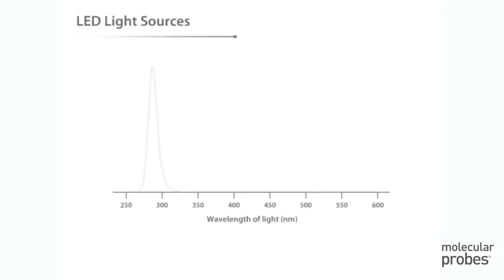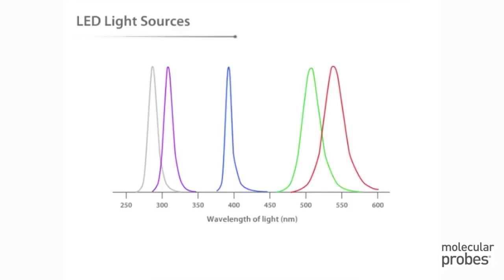LEDs are relatively new light sources for fluorescence excitation. Single-color LEDs are ideal for low-cost instrumentation, where they can be combined with simple long-pass filters that block the LED excitation and allow the transmission of the dye signal.